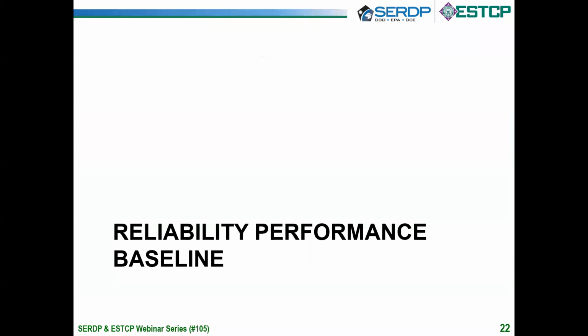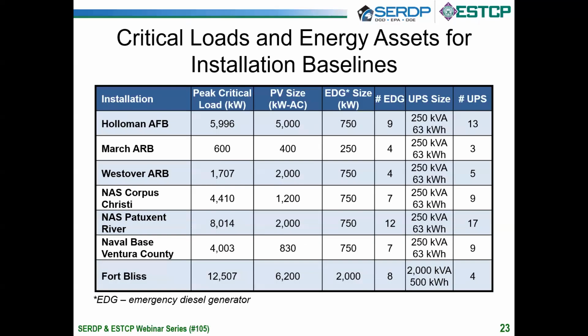I want to now turn to the first issue, which is important in understanding performance, which is a reliability performance baseline. Slide 23. First, let's set the stage on what this reliability is for. As I said before, we are considering 7 different installations that are all being modeled, and the key information on their loads and the distributed energy resources are shown on this slide. These range from very large installations, such as Fort Bliss, which is listed at the bottom of the slide, which has over a 10 megawatt peak load, to very small reserve bases, March and Westover, which are listed on the second and third row, which have on the order of only 1 megawatt of peak critical load.